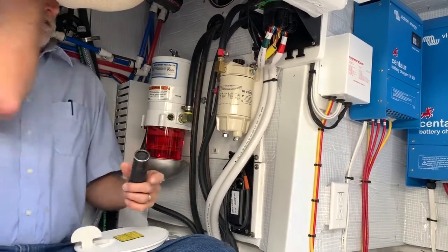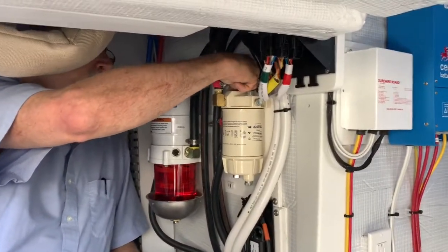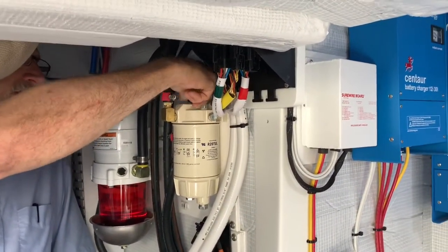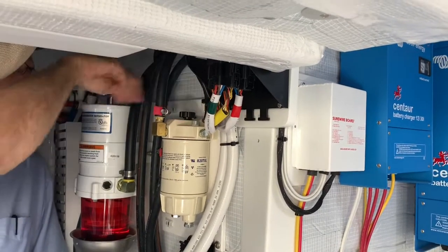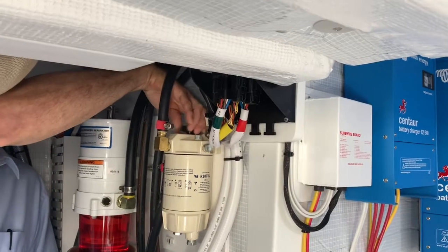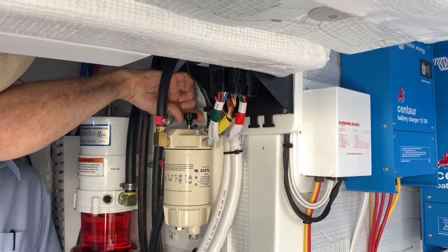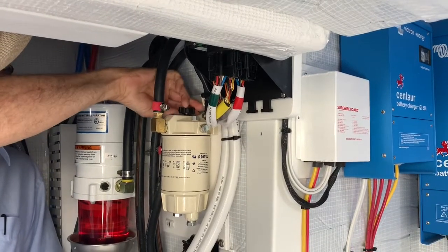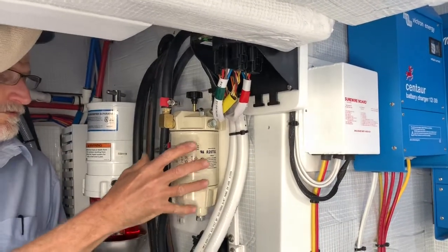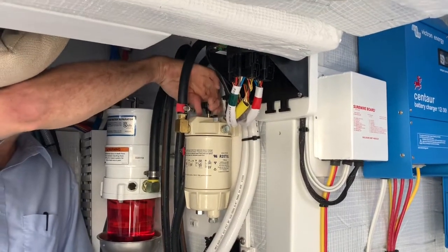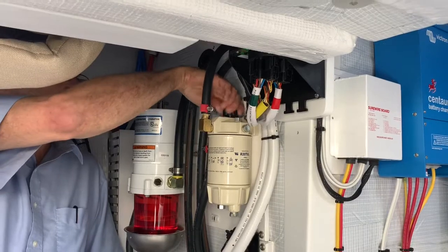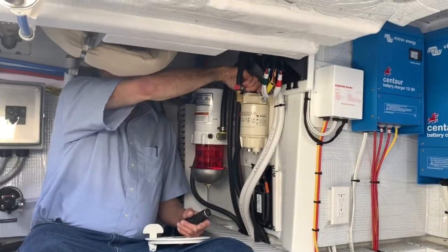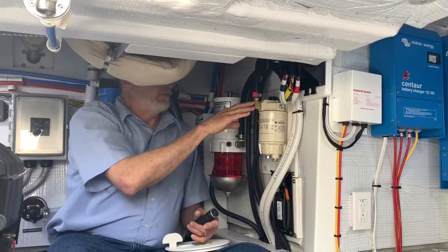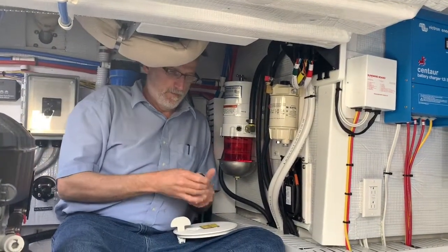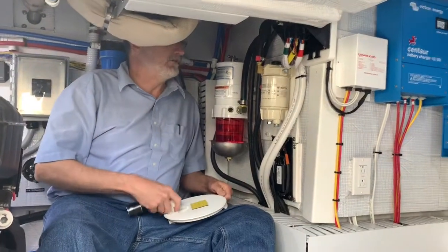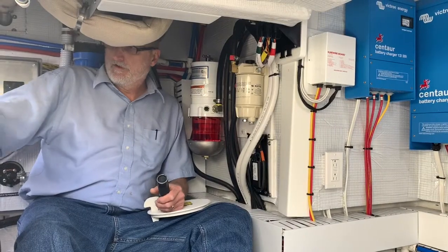The top of this fuel filter has a priming plug, so you don't need to pull the top off to get fuel back inside it. You just unthread this pump handle—I'll pull it up here and you can see the shaft, that's the pump handle. Of course it won't work very well right now because it's full of fuel, but if you need to purge the air out, you can just pump it until it gets stiff and then thread it back in, and that'll fill it with fuel. It will likely push the air through to the engine, but that's fine—the engine can pass air through it without any damage.